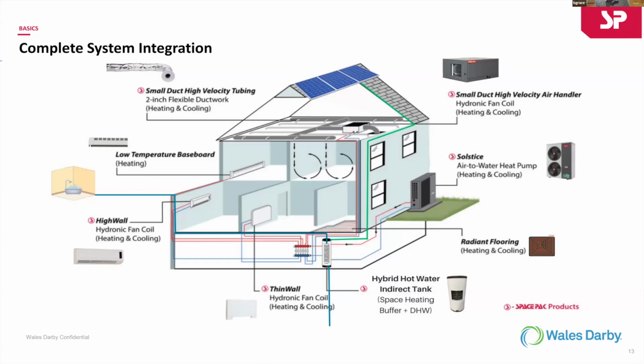You can have the air handler upstairs in the attic, and that is just done for cooling. So come the heating season, we're running hot water through the emitters in the house for heating. And then come summertime, we switch it over. It's running in reverse. The tank gets full of cold water, and we're running the cold water up to the air handler, and we're blowing cold air out through the air handler to cool the house. So it lends tremendous flexibility in the ability to design around the house and make the house comfortable. That's what we're looking at here.